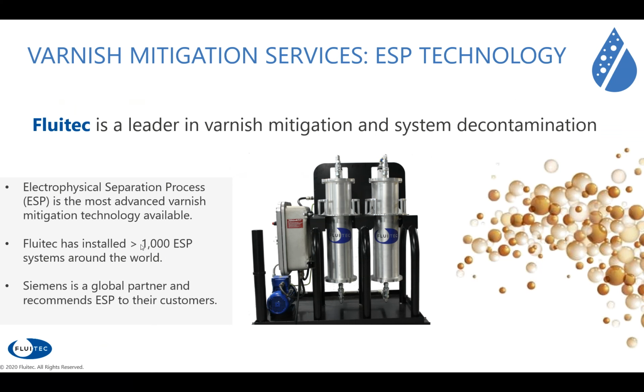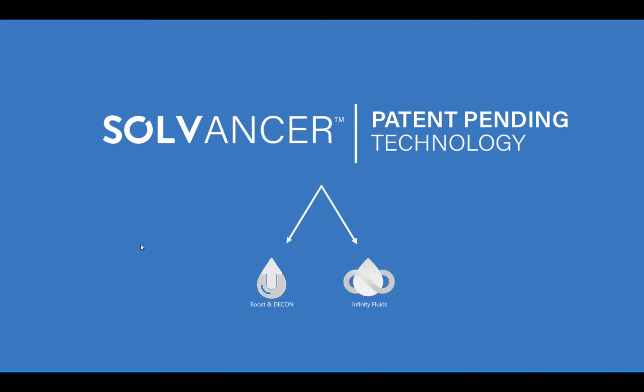So no need to cool it down or give it additional stress. It uses the in-service oil, keeping it clean, by treating it in a bypass or kidney loop of your oil reservoir. The resin technology is customized also as a function of the type of oil, the type of varnish, and the type of formulation. So please consult us. We will help you in selecting the right media mix. Once the oil system is clear and clean, you're able to keep the system clean.